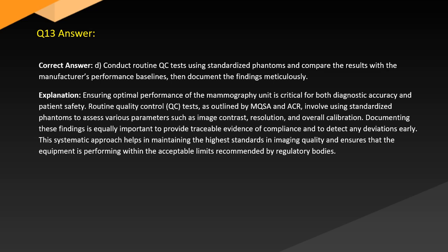Answer. Correct answer: D. Conduct routine QC tests using standardized phantoms and compare the results with the manufacturer's performance baselines, then document the findings meticulously. Explanation. Ensuring optimal performance of the mammography unit is critical for both diagnostic accuracy and patient safety.